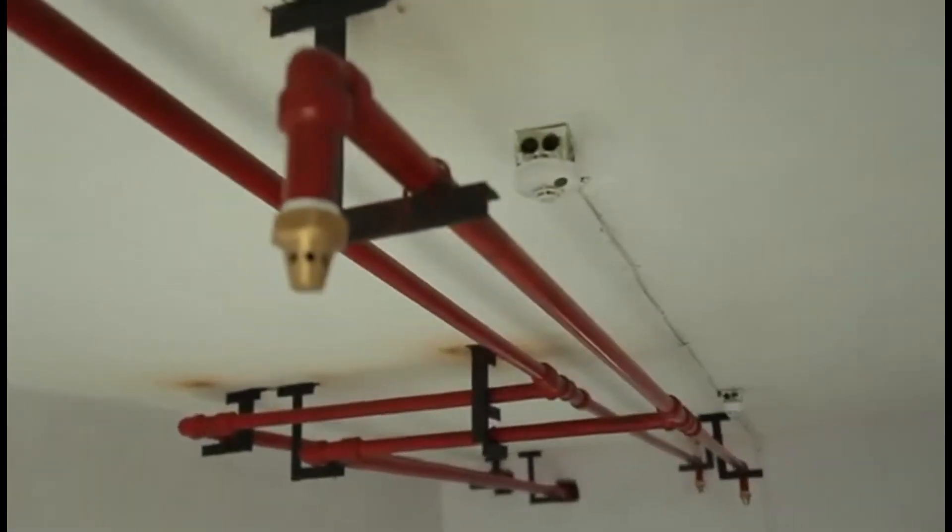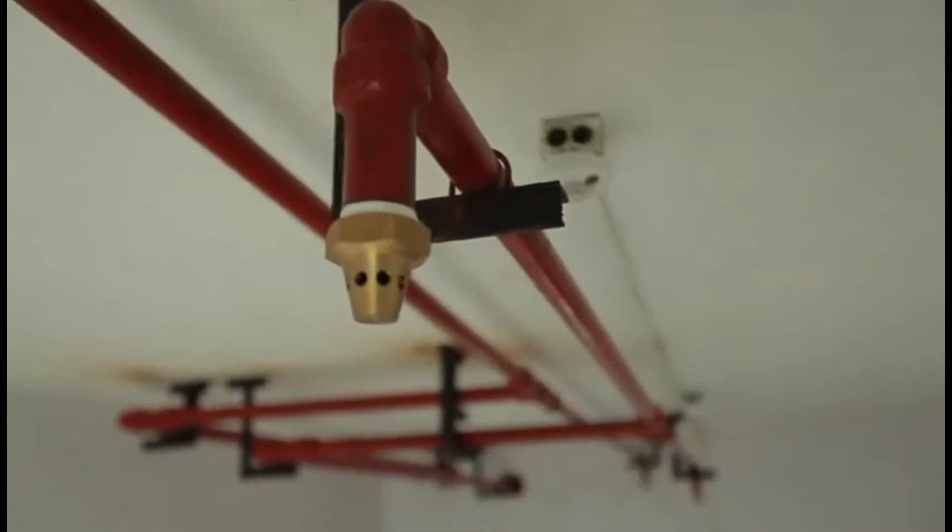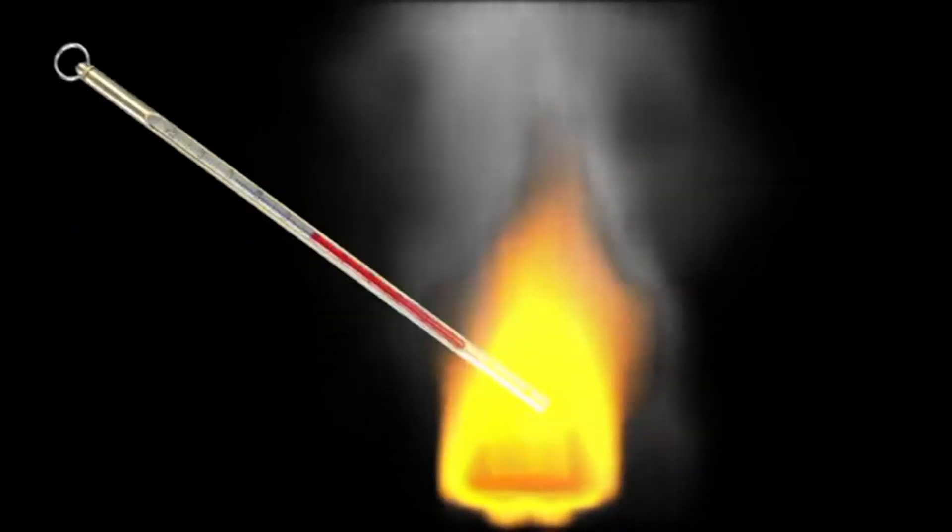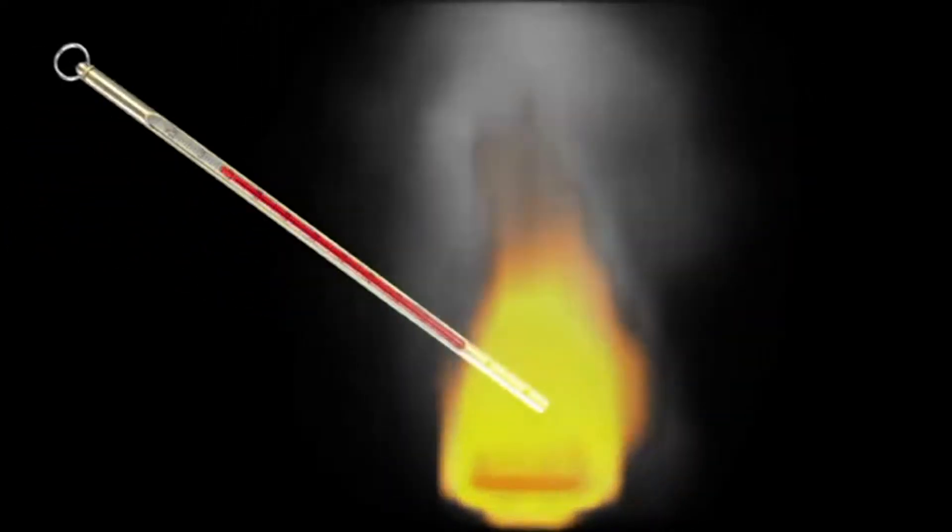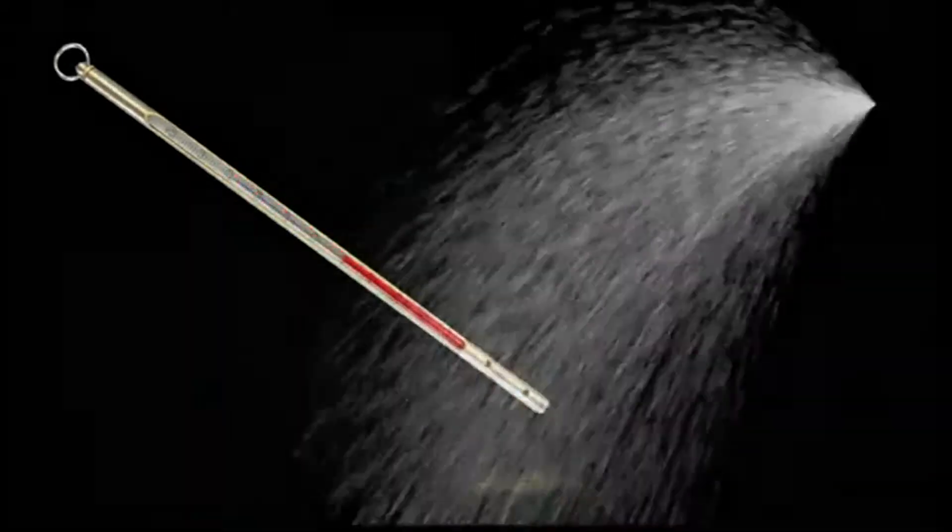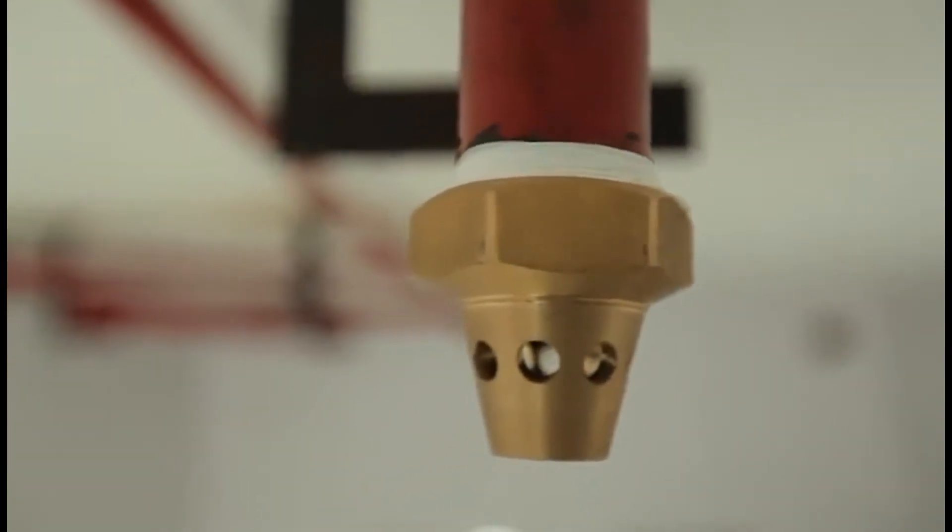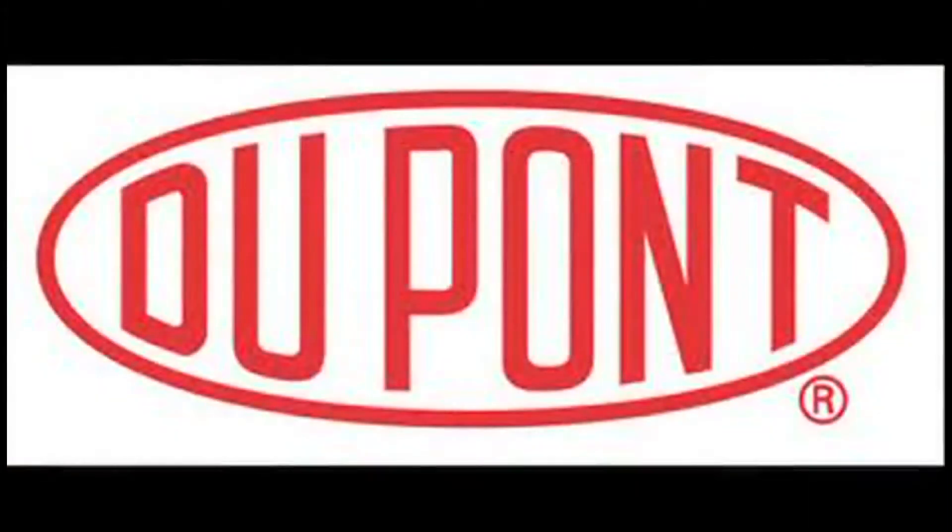FM 200 attacks a fire with a two-pronged approach. It absorbs the heat from the fire, bringing down temperatures and preventing reignition. The fluorine radical in FM 200 reacts with the flame, putting it out completely. This highly efficient extinguishing agent has been manufactured by world leader Dupont.